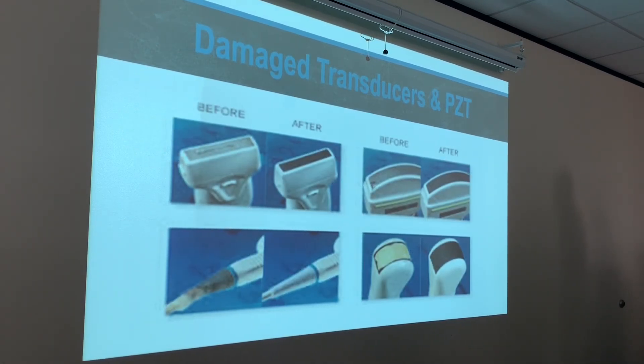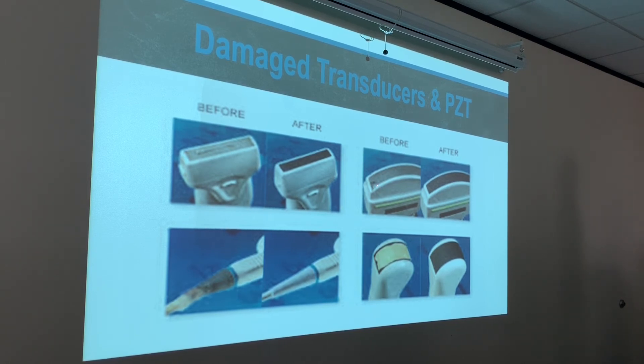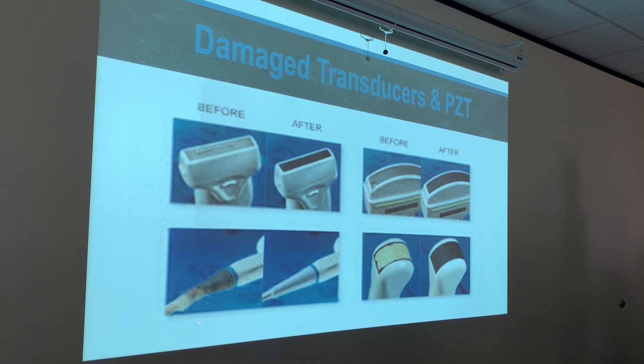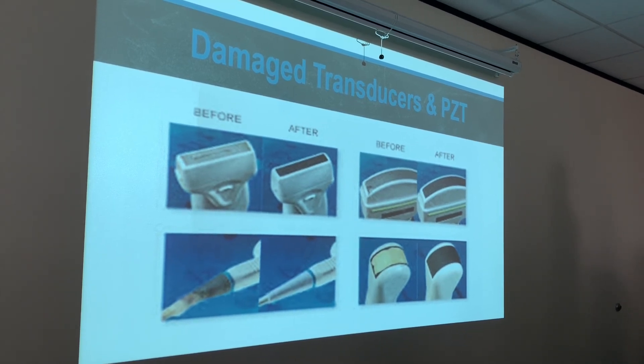Here are images showing a damaged transducer. You can see the matching layer is completely off, exposing the PZT crystals much closer to the surface than they should be. The matching element is chipping away — if you see this, it's degrading your images, so please let somebody know. There's a C5 transducer in the lab I found recently where the wire is being exposed, which could cause an electric shock, so I need to take it out of service today.